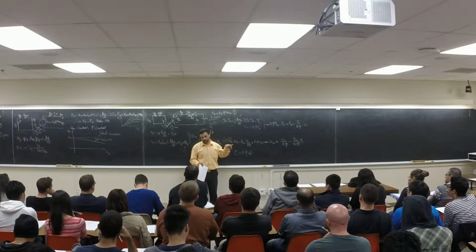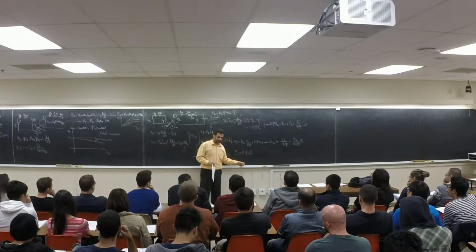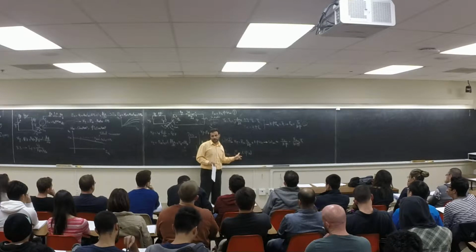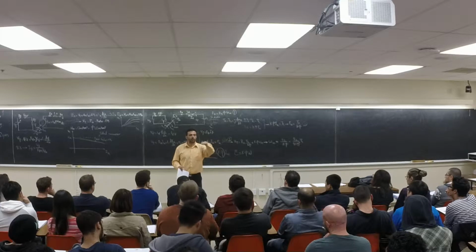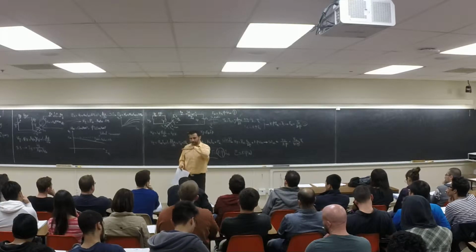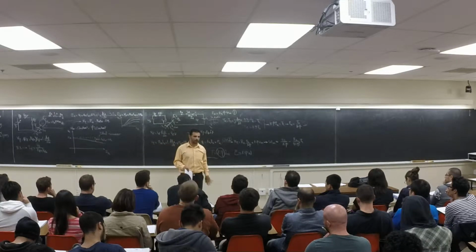It's going to kill your machine. So basically, if you go up on this one, you have to go down with this one. You have to reduce this one to keep the voltage constant. If you go above base speed, you keep the voltage constant. You don't go more. But under the base speed, you can have a variable voltage from 0 to the nominal voltage.